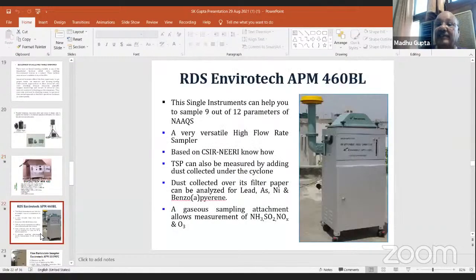Later on, when it was realized that we need to measure respirable dust, we developed this respirable dust sampler with know-how from NEERI Nagpur. Why did we go to NEERI Nagpur? Because we wanted this equipment to remain portable and compact, and it should have a separation device which is certified and verified, so that nobody doubts that whatever you are measuring out of this respirable dust is correct. So they developed a small cyclonic device, which we inserted into our high volume sampler and produced this almost same size device. This was such a unique development that it offered mobility to the instrument, and because of this mobility, the measurement of respirable dust became very easy and convenient throughout the country.